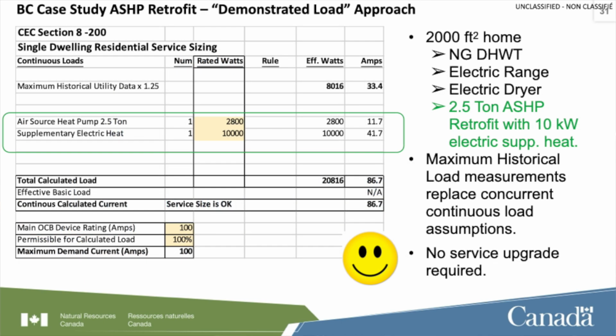If we throw that into our calculations: the maximum historical data plus 25% gives us 33.4 amps. Then we add the air source heat pump and supplementary electric heat system, and we're still within our allowable load. This isn't the norm yet in Alberta, but I think at some point we'll see it, since it's a great way for utilities to manage peak usage — and it gets the approval of Natural Resources Canada.